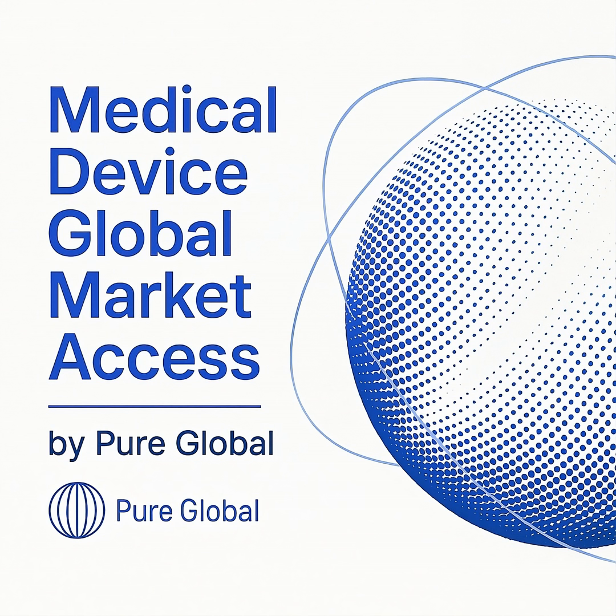Health Canada has its own sovereign regulatory framework, the Canadian Medical Devices Regulations, or CMDR, and you must meet its specific requirements. First, your device must be classified according to Health Canada's risk-based system, which categorizes devices into Class 1, 2, 3, and 4. A PMA-approved device, being a high-risk product, will almost certainly fall into Class 3 or Class 4 in Canada. All devices in these classes require a medical device license, or MDL, before they can be sold.